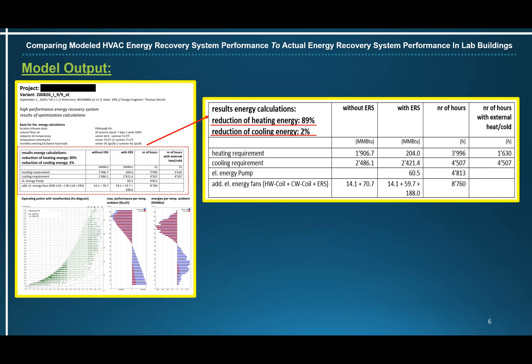Let's look at some model output — first the results of the energy calculation values. There's a blow-up of these values on the right side of the screen. This table shows the annual heating, cooling, and energy consumption results with and without energy recovery. The annual heating requirement without energy recovery is 1,906 million BTUs; with energy recovery it drops to 204 million BTUs. The annual cooling requirement without energy recovery is 2,486.1 million BTUs. The last two lines show pump and fan energy, and the table also shows the number of heating and cooling hours per year.